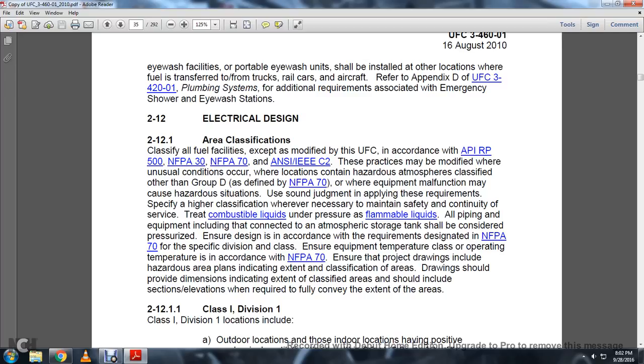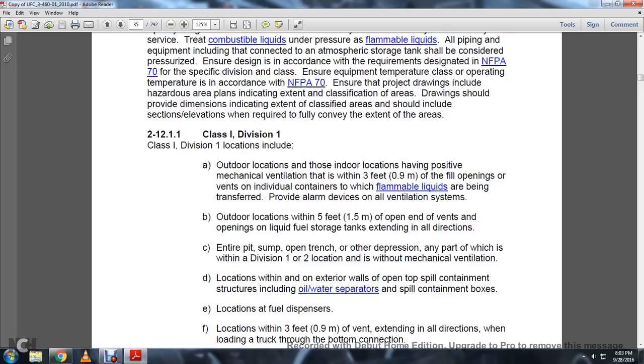Ensure design is in accordance with the requirements of NFPA 70 for the specific divisions and class. Ensure the equipment temperature class or operating temperature is in accordance with NFPA 70. And ensure the project drawings include the hazardous areas and indicate the extent of the classification of areas. Drawings should be provided with dimensions indicating extent. Classified areas should include sections and elevations as required to fully convey the extent of the area.